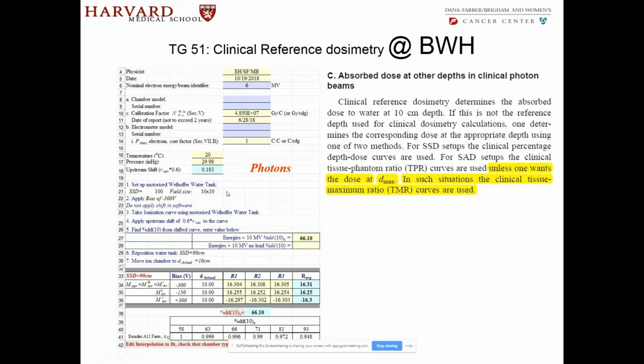So this is for photons. Our final result is the following. After we do the measurements, per MU, it's 1 centigray, and this is 0.68% off, which is acceptable. So 1 centigray corresponds to 1 MU. This is the TMR value from our measurement, and you can do the same. What I have given you on this slide are all the details of how a procedure can be developed. Notice the calibration factor is included here.